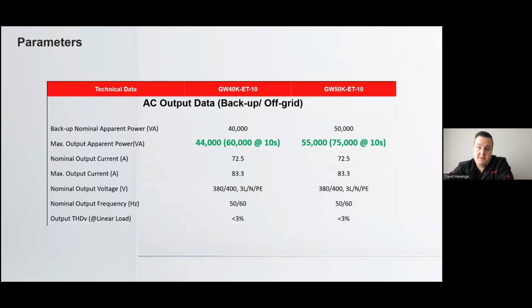Then for the backup side, for backup operation on our inverters, we do require the STS, which is an additional component. The STS is a smart transfer switch, which I'll show shortly. With that smart transfer switch, you can see the backup output can do a constant 55 kilowatts on our inverters, and on the 50 kilowatt we can do up to 75 kilowatts of load for 10 seconds. That's quite a massive overload capacity. So that's for startup on motors and things like that.